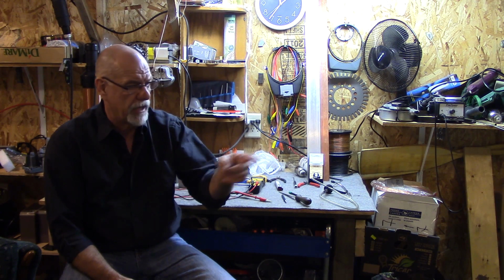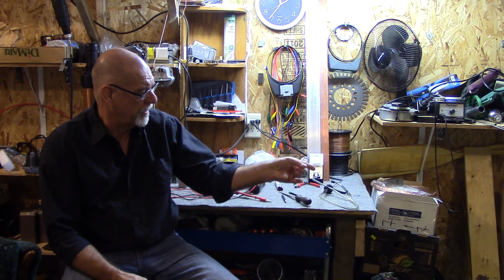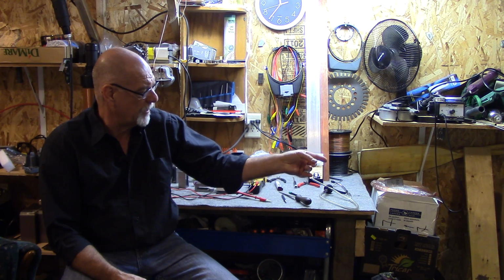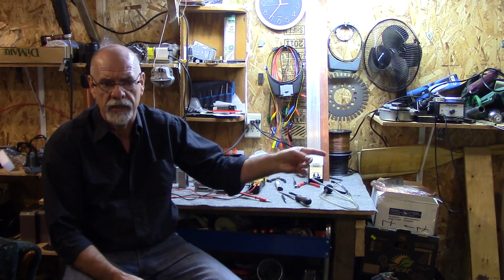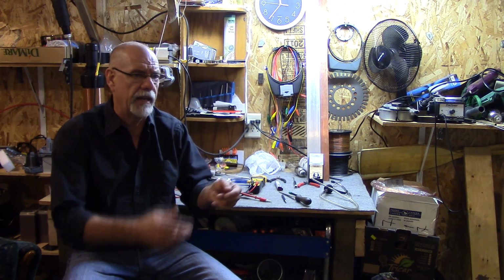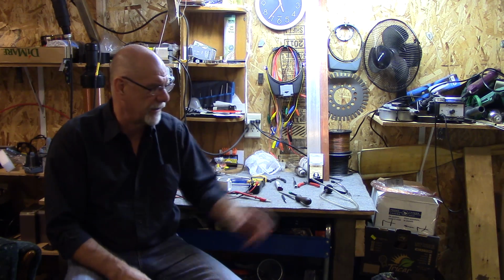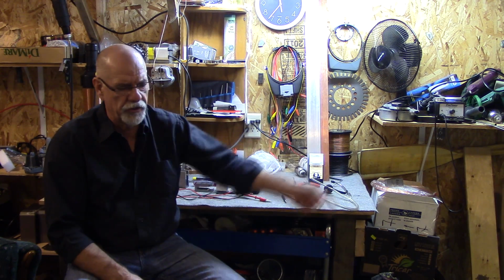I'll push that right through my transformer on one leg, so I can see what's coming out on my X1, X2 and voltage, because my generator will probably be around 3,000 to 4,000 volts, and I don't have a meter for that. A 5,000 volt meter is too expensive, so I can down-volt through the transformer and see what I'm doing.